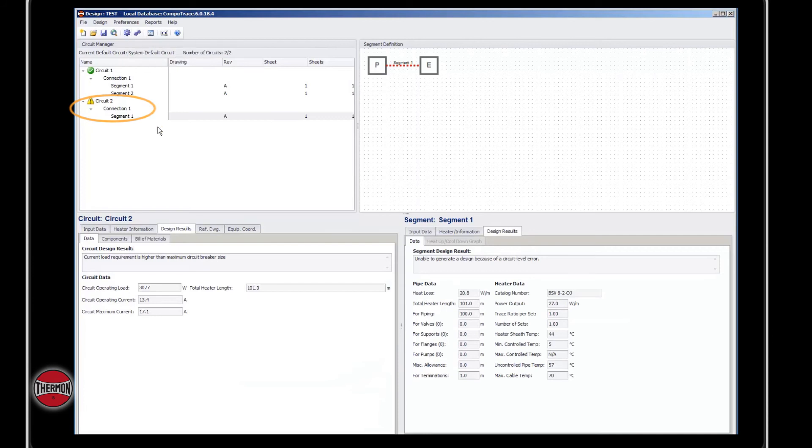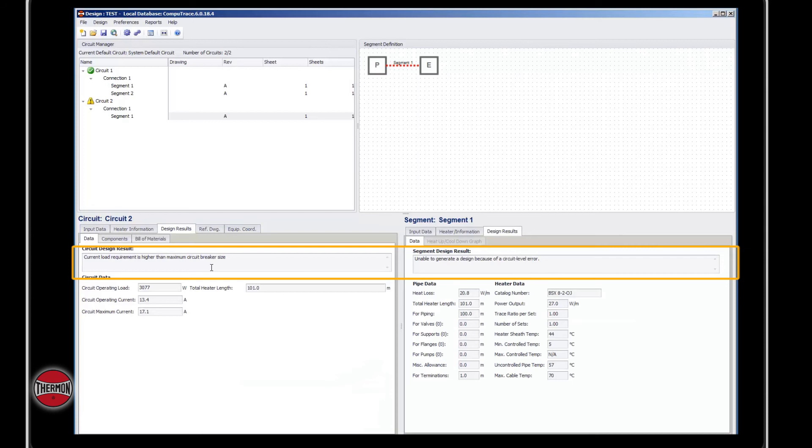To follow the error, you can go down to the circuit and segment window. You can see on the segment window it says that you were unable to generate a design because of a circuit level error. This means you go over to the circuit window, and it says your current load requirement is higher than the maximum circuit breaker size.